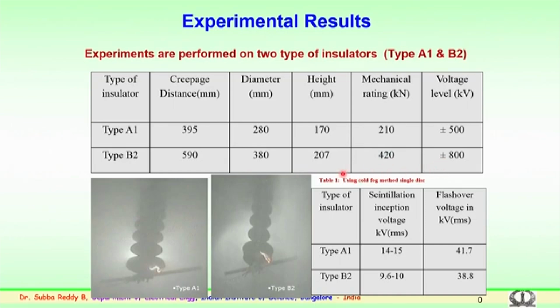Various experiments as per the standards, using cold fog, steam or spray methods, have been followed, and the insulators are coated as per the standards before the experiments are conducted. The intention is to see how the inception of scintillations or partial arcs which originate from the pin junction occurs and how to arrest this. This was one of the studies wherein a method was developed to reduce the scintillations or partial arcs for insulators used in high voltage DC systems.